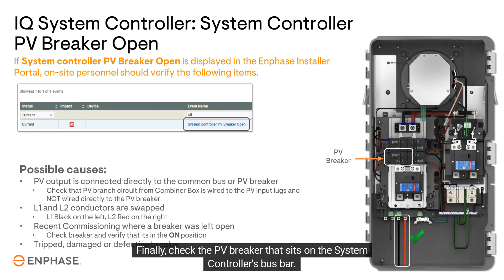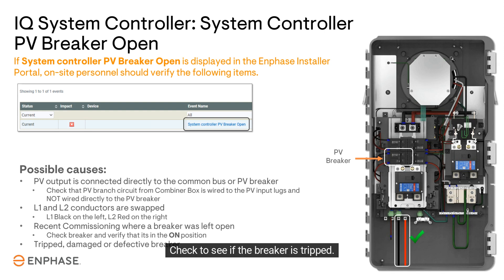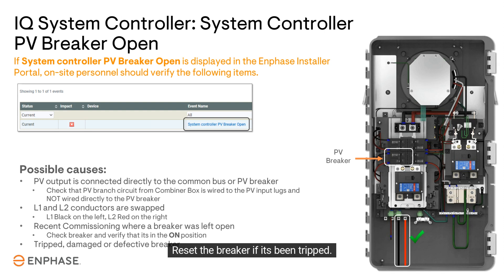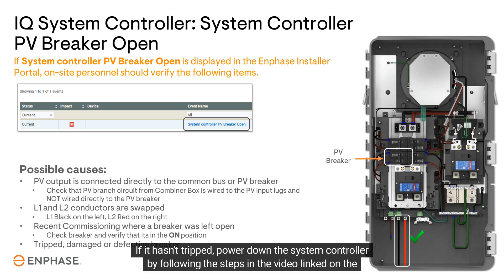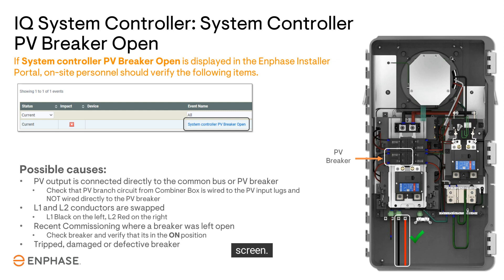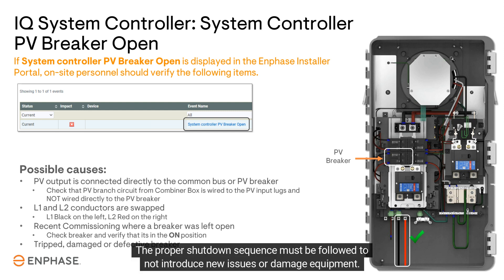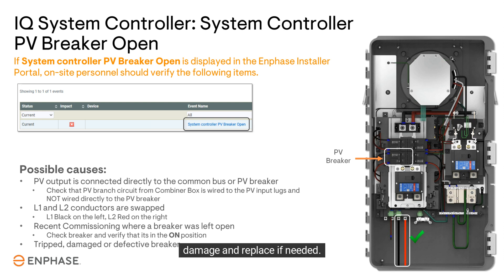Finally, check the PV breaker that sits on the system controller's bus bar. Check to see if the breaker is tripped and reset the breaker if it has been tripped. If it hasn't tripped, power down the system controller by following the steps in the video linked on the screen. The proper shutdown sequence must be followed to not introduce new issues or damage equipment. Once the system controller no longer has power, pull the PV breaker from the bus bar and inspect it for damage and replace if needed.